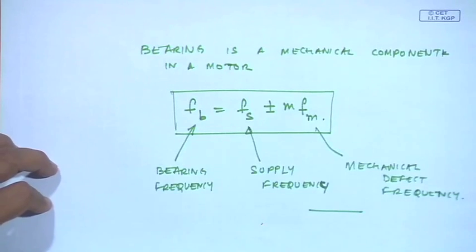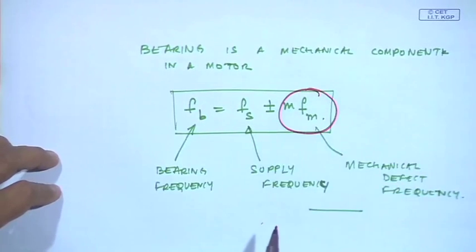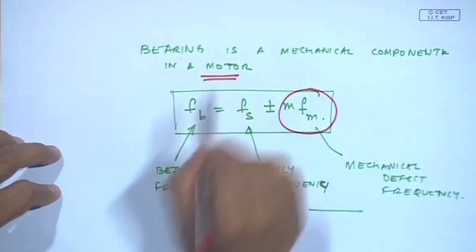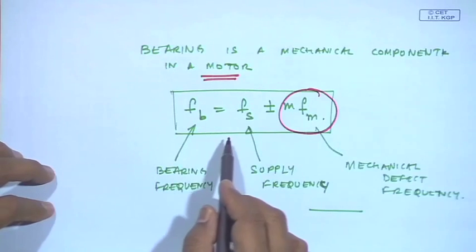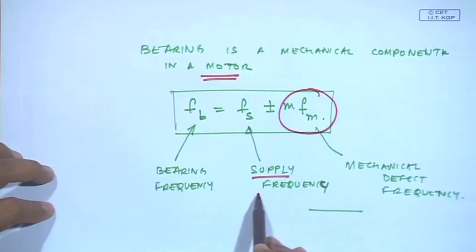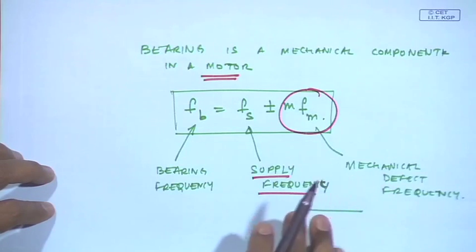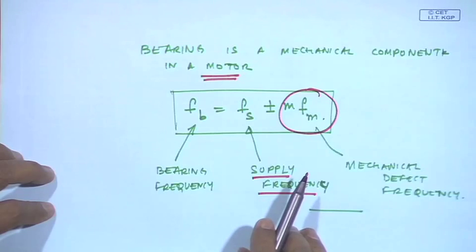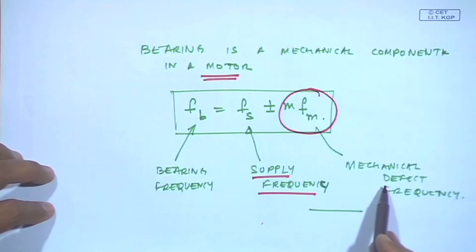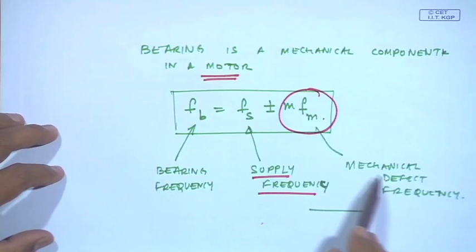This gives us a clue that if I have any mechanical defect frequency in a system which is being driven by an electrical motor, by looking at the motor current spectrum, I can see side bands around the supply frequency. If I have a system driven by an electrical motor and this mechanical system has defects, I will see these defect frequencies come as side bands around the supply frequency.